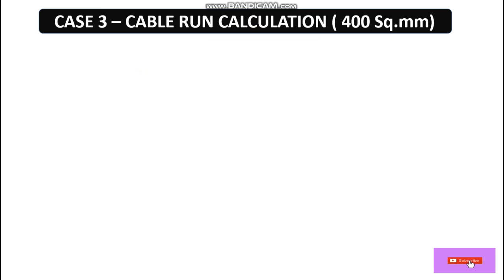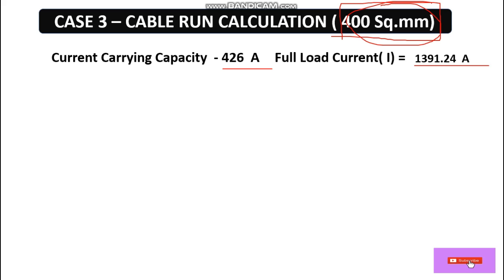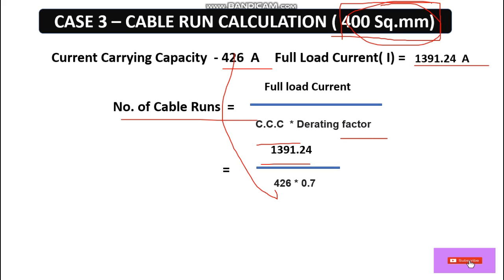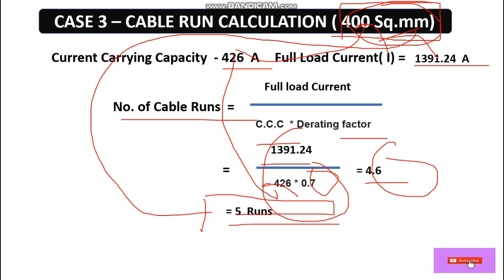Case 3: Let's decrease the size further to 400 square mm. From the cable catalog, the current carrying capacity of 400 square mm is 426 ampere. Full load current is 1391.24 ampere. Number of cable runs = 1391.24 / (426 × derating factor) = 4.6 runs, so 5 runs are required. For 400 square mm cable, 5 runs are needed.